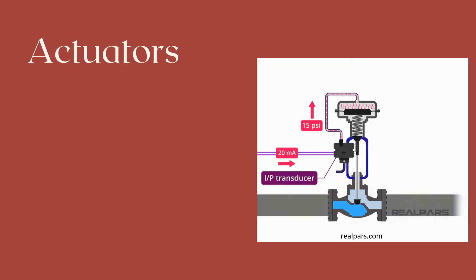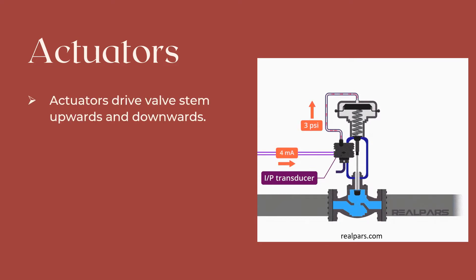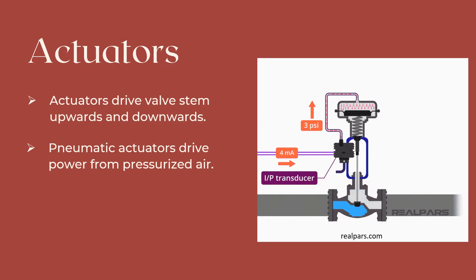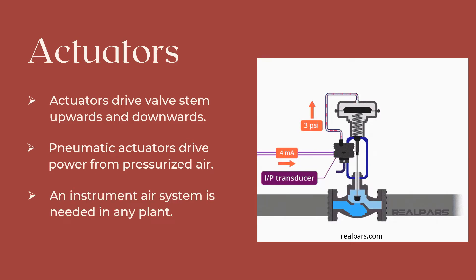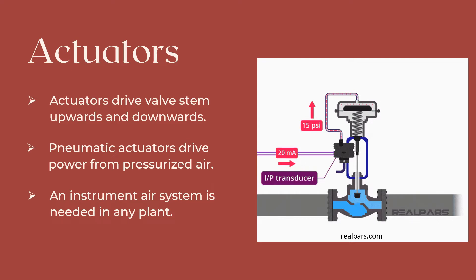So how is the control valve connected to the control loop? Control valves are equipped with actuators. Actuators move the valve stem upwards and downwards based on the signal received from the controller. Actuators are mostly pneumatic, which means they drive power for the valve operation through pressurized air. This means that any plant would need an instrument air compressor, receiver, and piping header to supply air to all control valves in the plant.